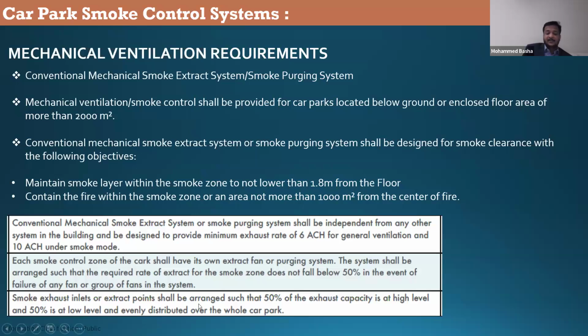But there is an exemption for residential buildings. You do not need to have the low level exhaust. You can have only high level. It is also mentioned in the QCDD standards. So it is not always that you need to drop the duct down to the low level to take 50% from here and 50% from there.